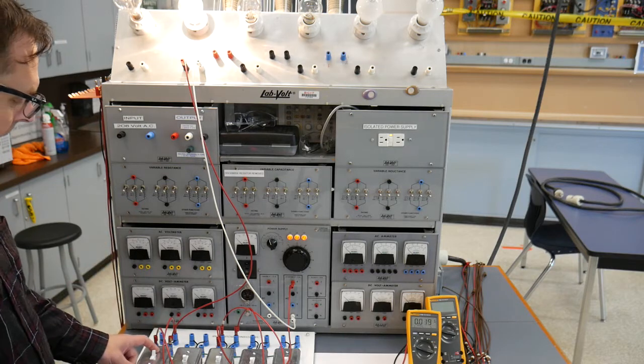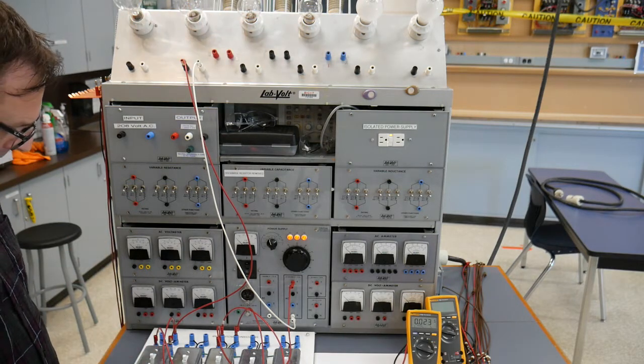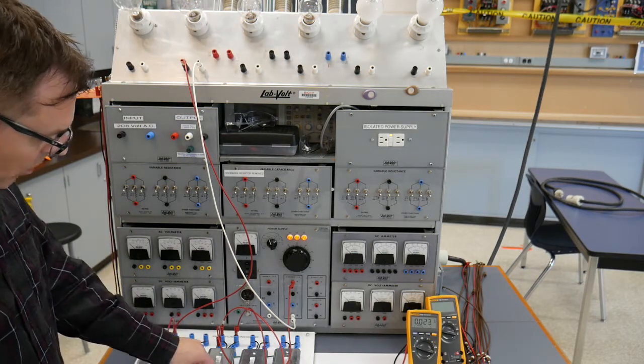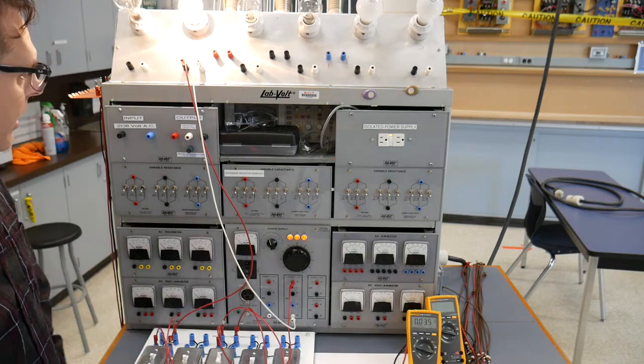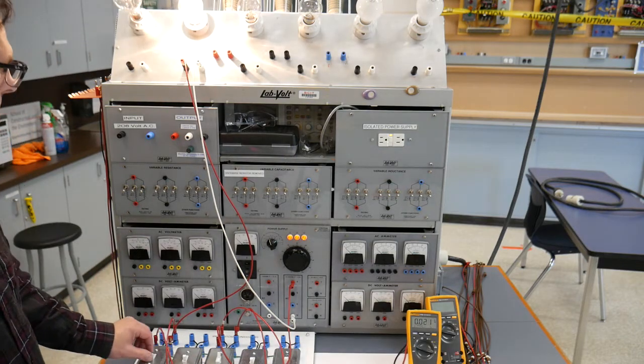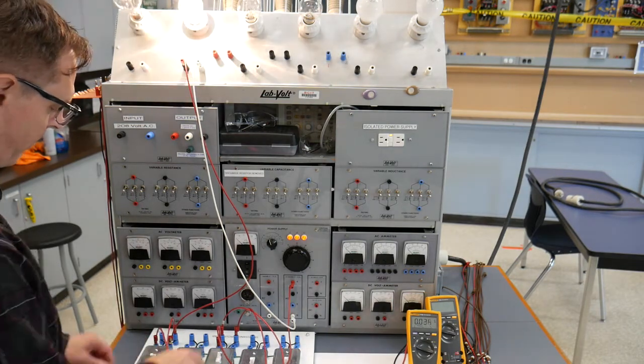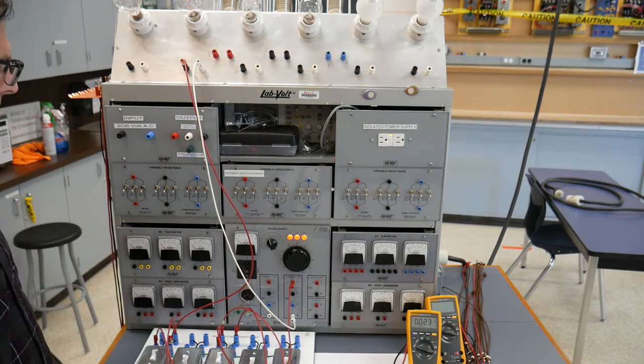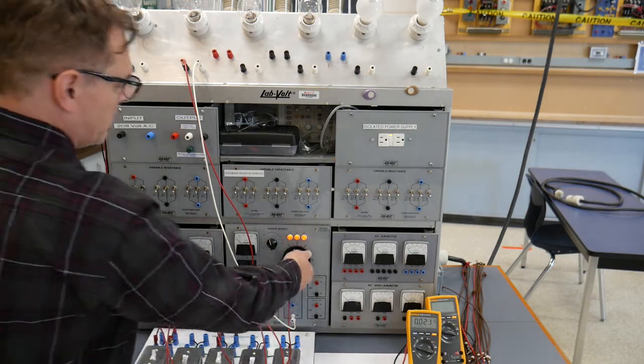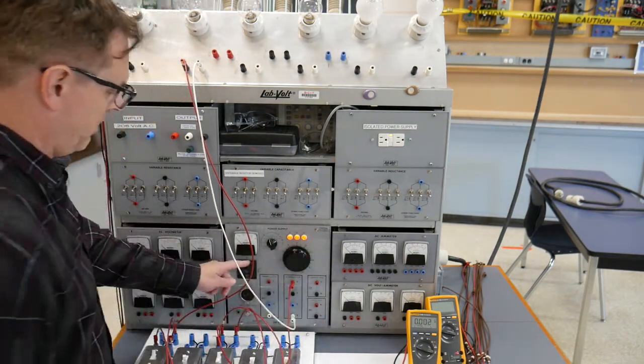So the light's on right now. I turn it off at that location. Go to the second location, turn it on. Yes, that works. Come back to the first location, turn it off, and it works. And I should just be able to keep rotating back and forth. And we magically have the first 3-way switch, or 3-way circuit working.